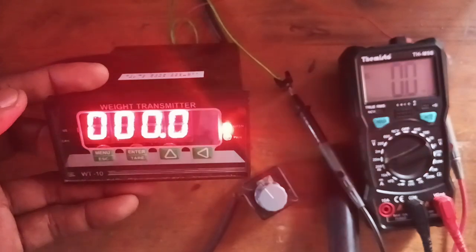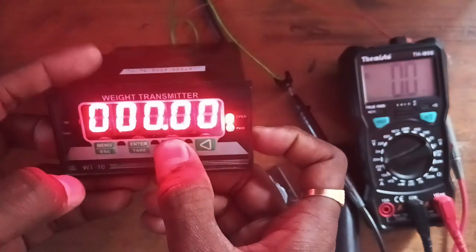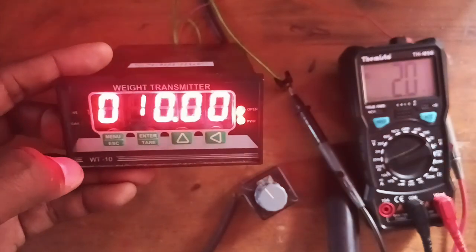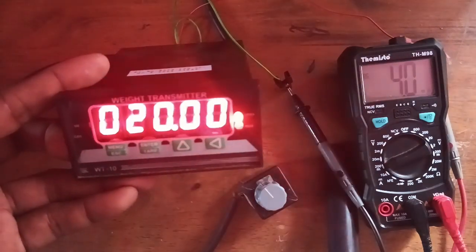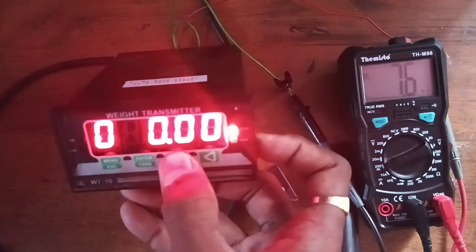If you want to check the analog output, press enter. As already explained, 0 to 100 kg is configured for 0 to 20 milliampere. I am going to simulate 10 kg — that means you should get 2 milliampere. Now I am increasing to 20 kg: 4 milliampere. 30 kg: 6 milliampere. 40 kg: 8 milliampere.